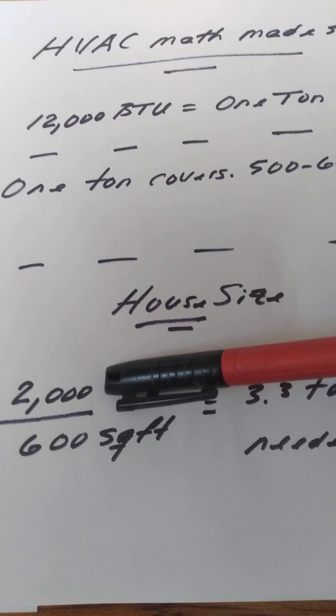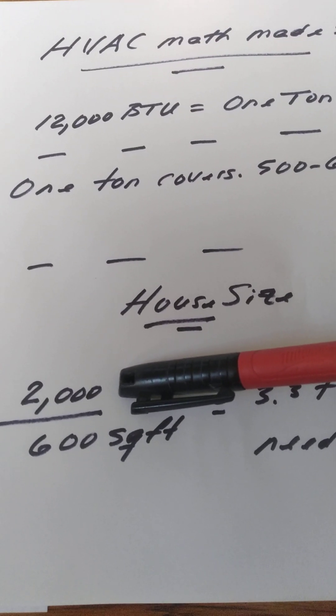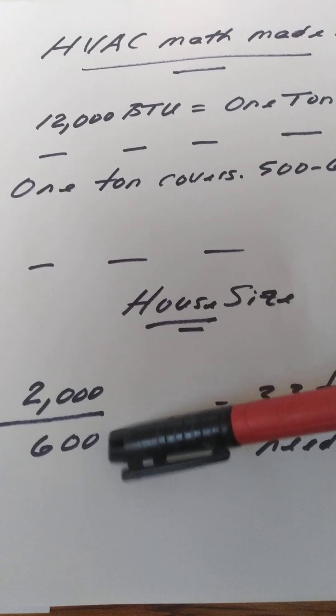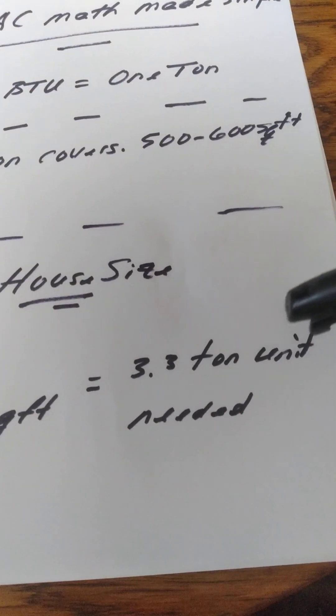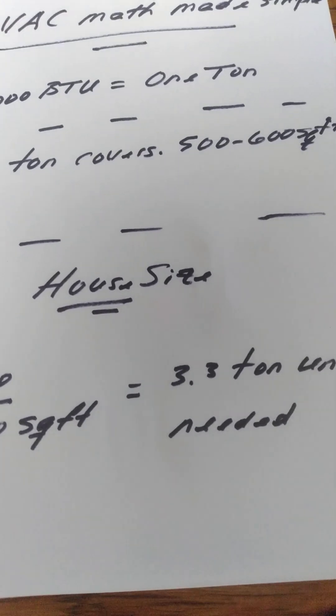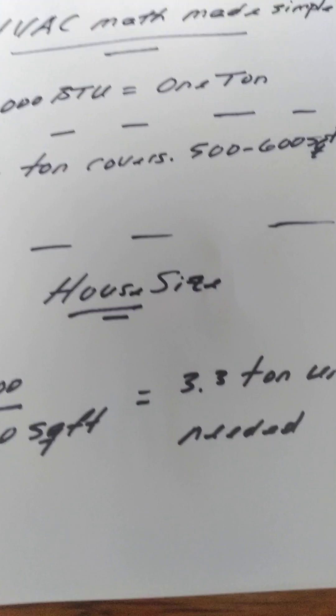You put this number here. This house here, for just a hypothetical, I put in 2,000. 2,000 divided by 600 equals 3.3 ton unit needed. So one in this case would need around a three to three and a half ton unit to heat and cool roughly a 2,000 square foot house.